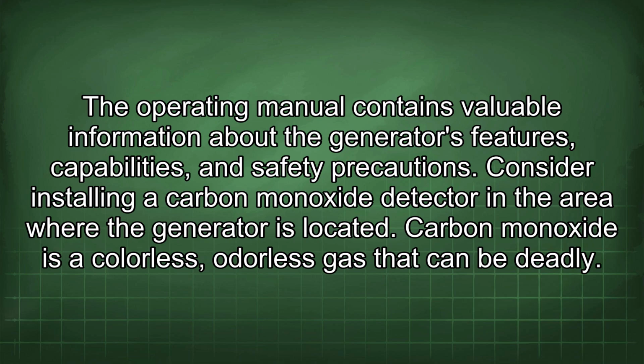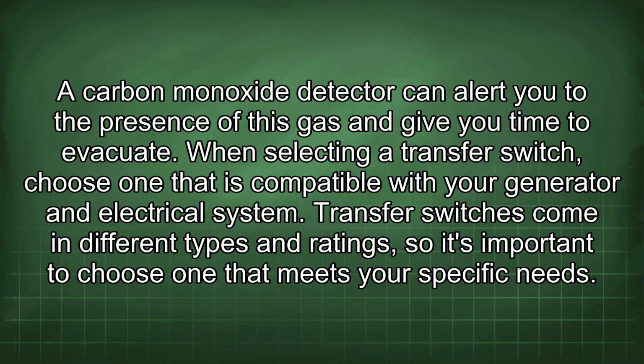Consider installing a carbon monoxide detector in the area where the generator is located. Carbon monoxide is a colorless, odorless gas that can be deadly. A carbon monoxide detector can alert you to the presence of this gas and give you time to evacuate. When selecting a transfer switch, choose one that is compatible with your generator and electrical system. Transfer switches come in different types and ratings, so it's important to choose one that meets your specific needs.